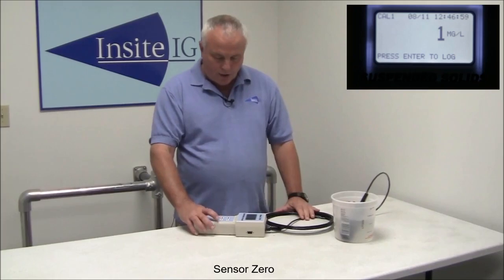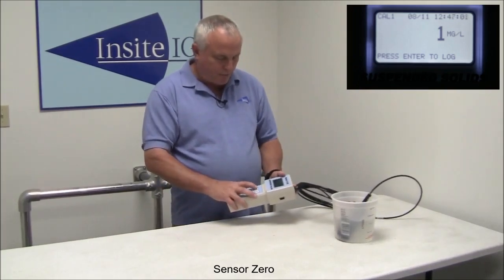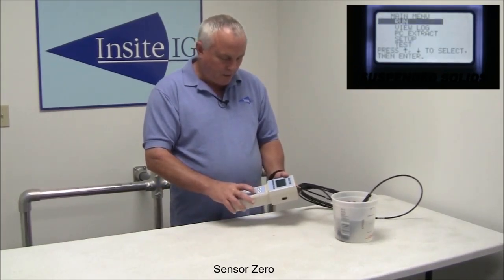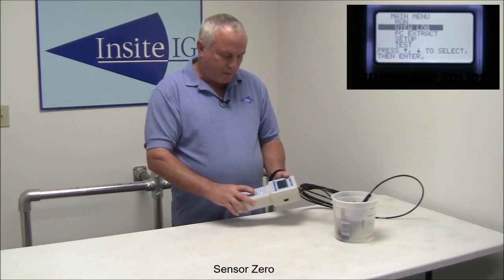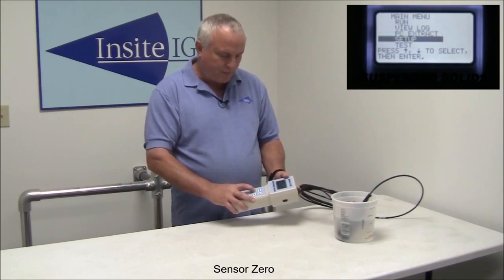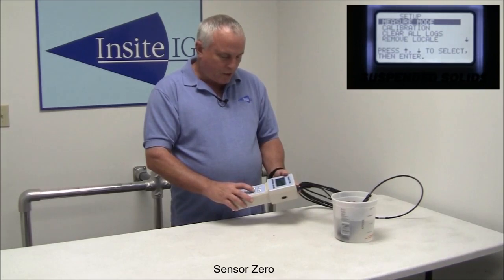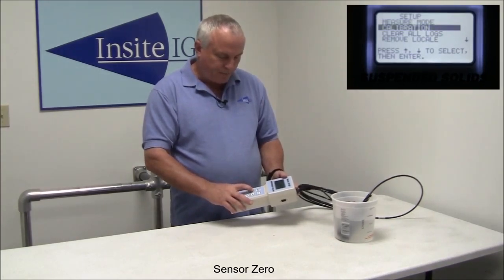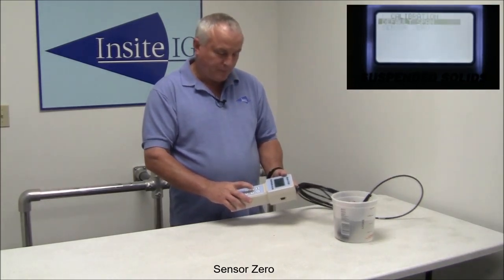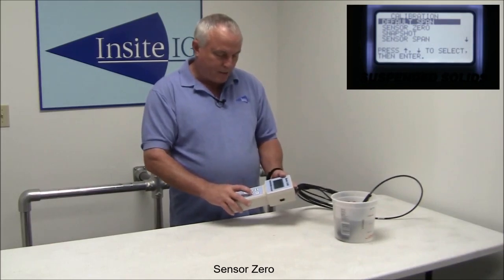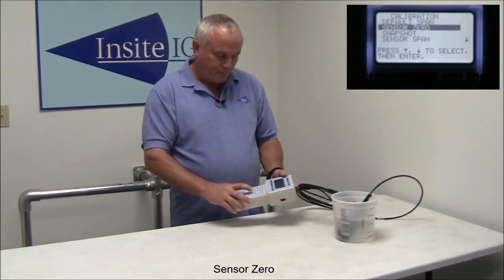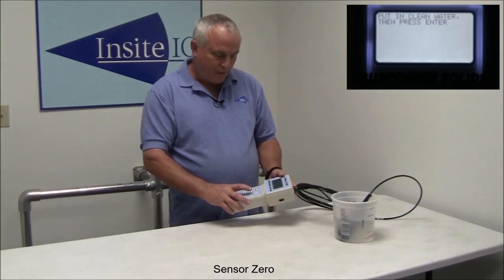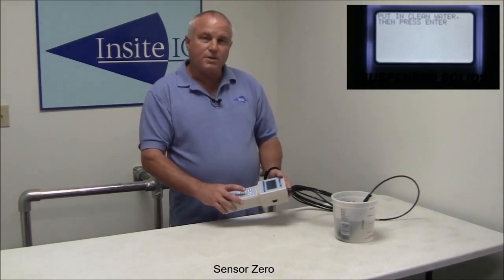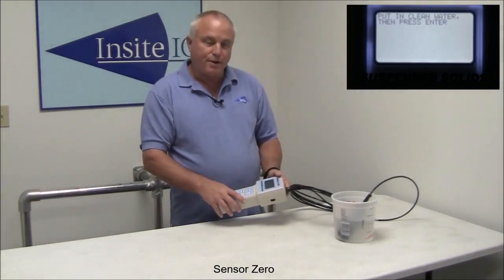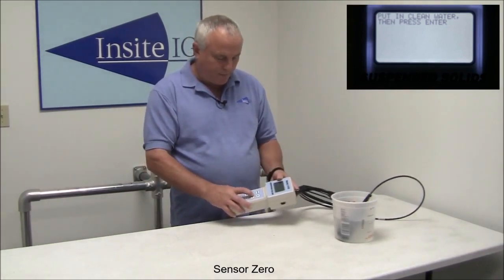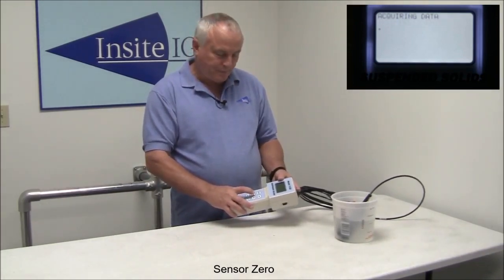And then with the unit on, you would just come through and hit the menu button. Scroll down to setup, press enter. Scroll down to calibration, press enter. Scroll down to sensor zero, press enter. And it's going to come up with a message that says put the sensor in clean water, then press enter. We're already in clean water, so you would press enter.